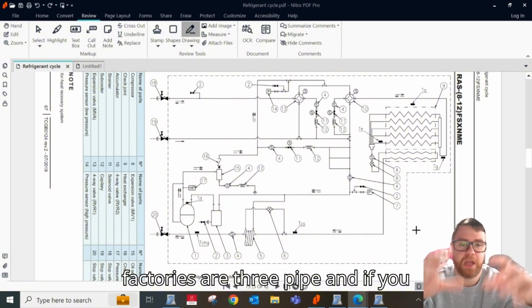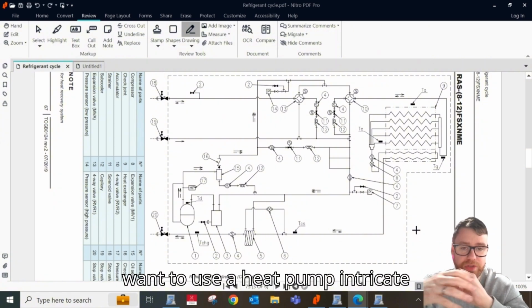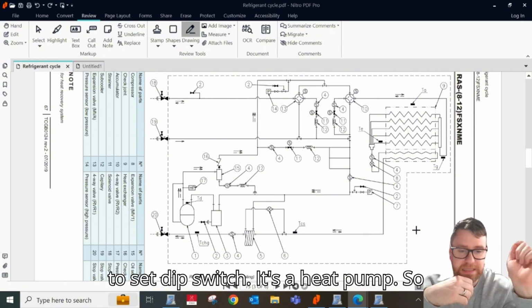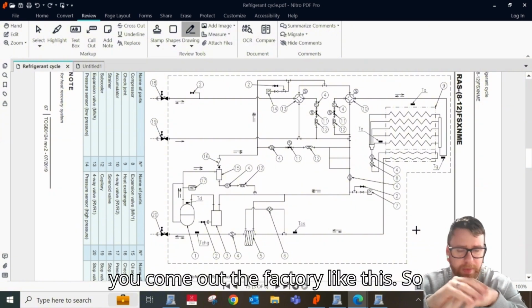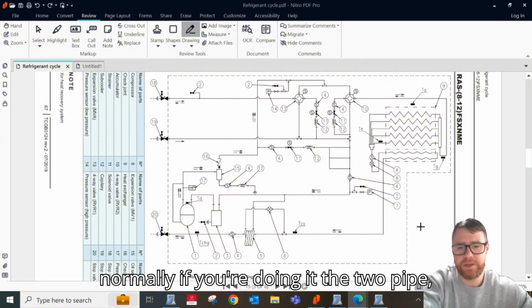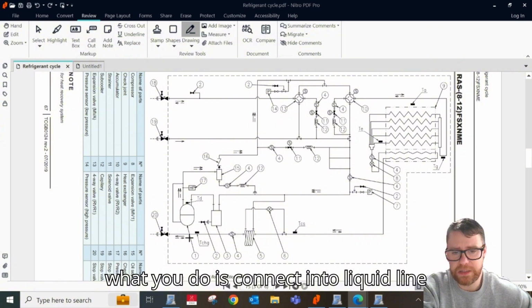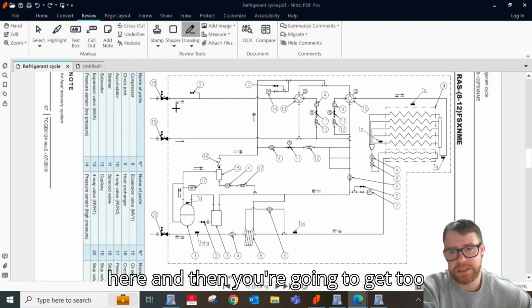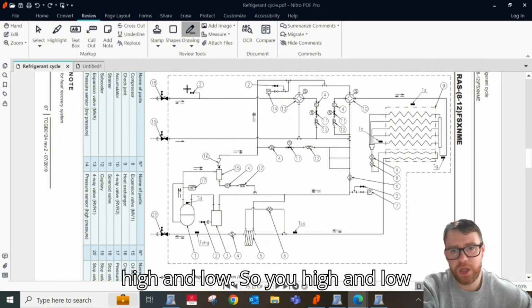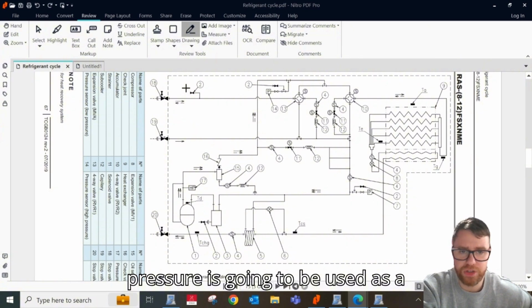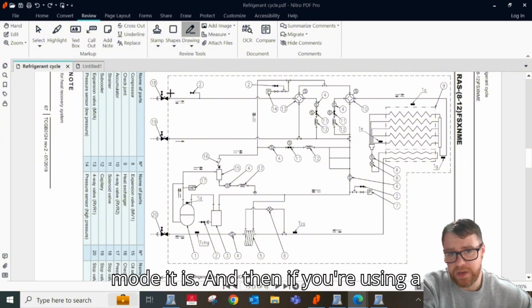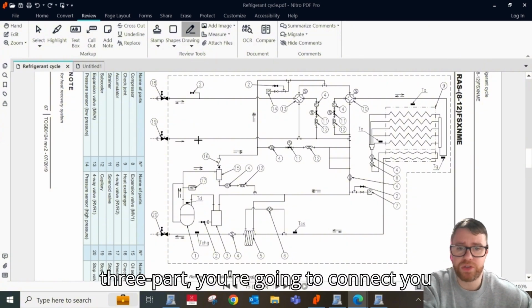Basically, these come out of the factory as a 3-pipe, and if you want to use it as a heat pump, you just set a dip switch, and it's a heat pump. So they come out of the factory like this. Normally, if you're doing it as a 2-pipe, you connect into your liquid line here, and then you connect to your high and low. Your high and low pressure is going to be used as a discharge and suction, depending on what mode it is. And then if you're using it as a 3-pipe, you're going to connect your suction pipe to the common suction.